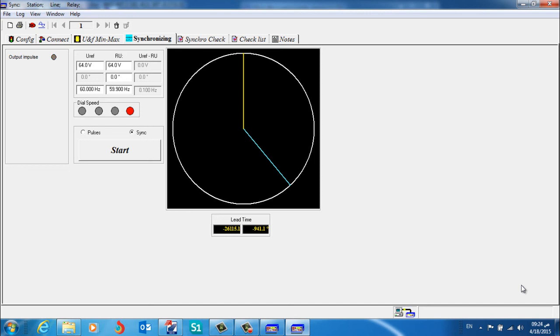Okay, if we make this one VT MCB trip and inject, nothing. Okay, but now we test two conditions for this to prevent or block the synchronization: breaker close and VT MCB trip.